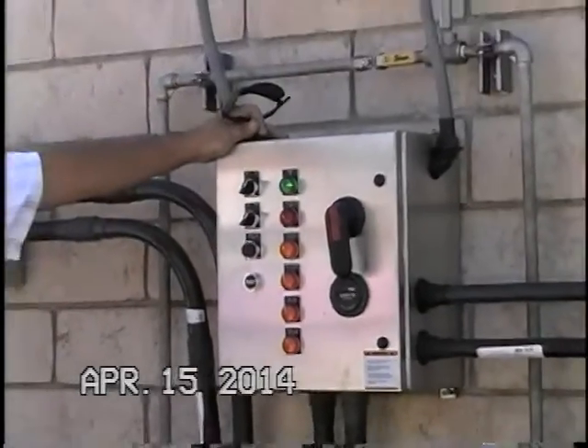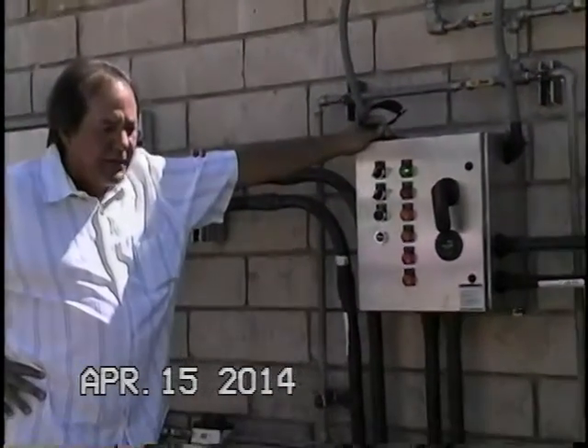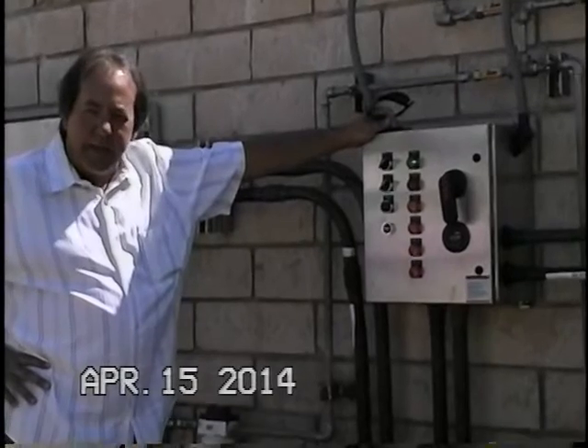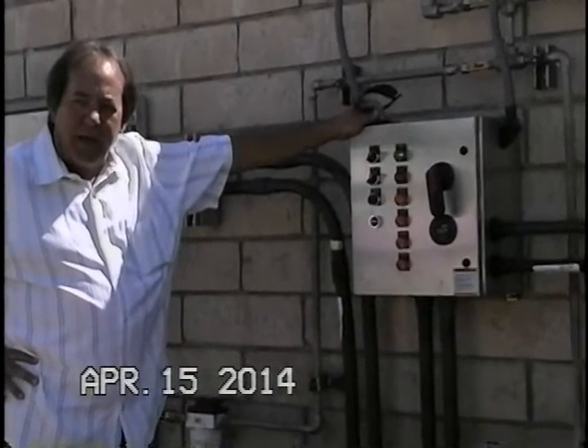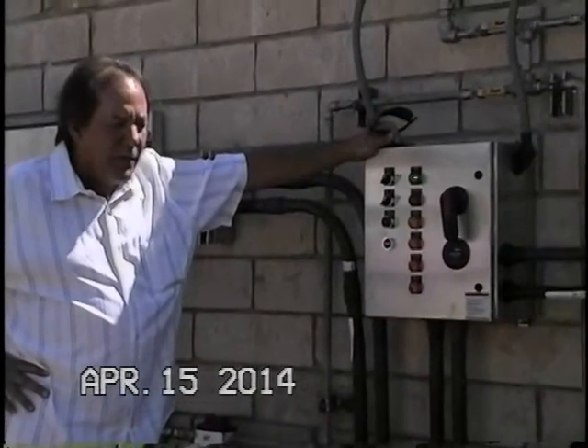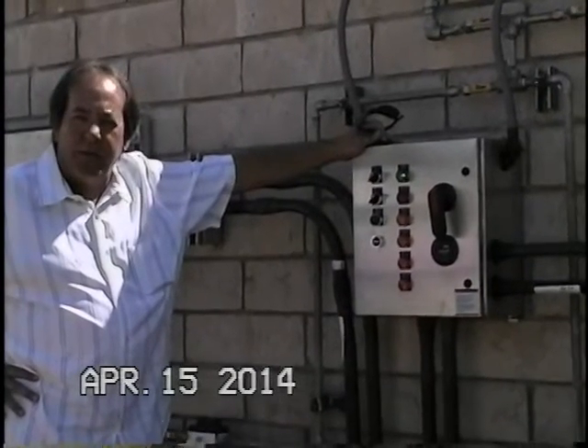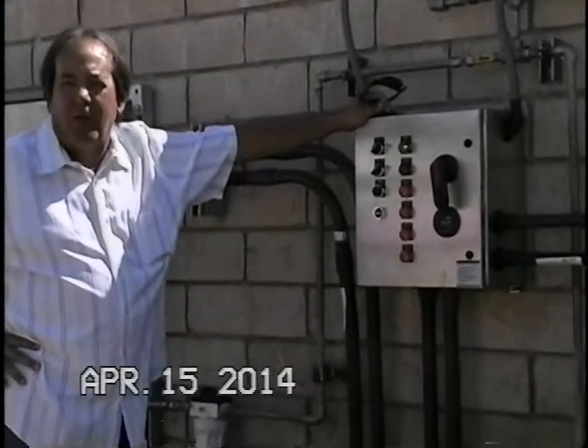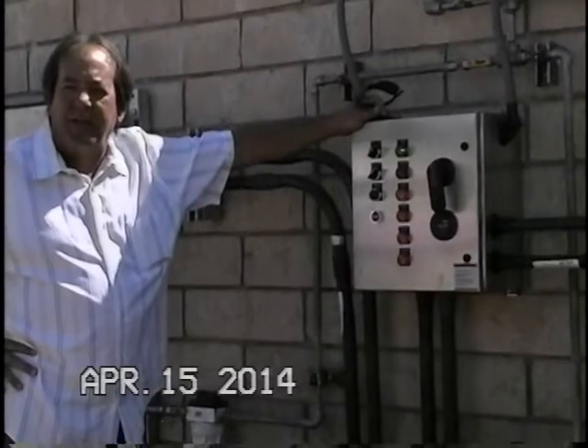So that's all that you should expect, because I've noticed that it takes about 45 minutes once we get to the add air. This compressor is going to run between about 30 and 45 minutes, up to an hour max, before it'll satisfy the liquid level.